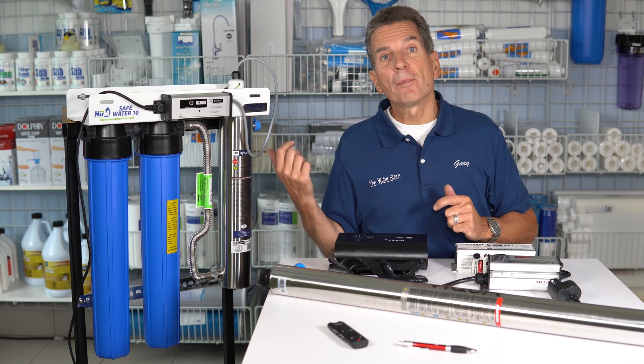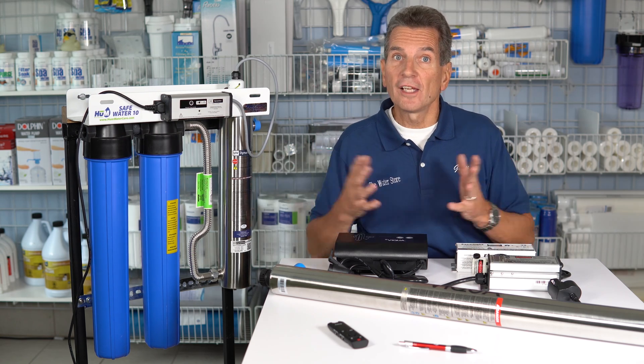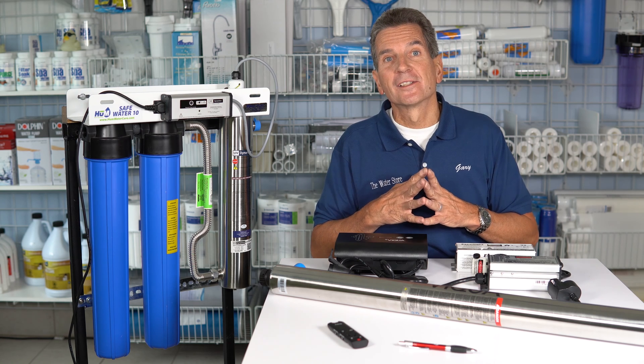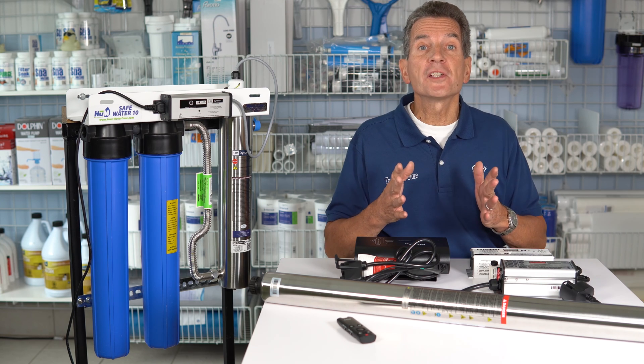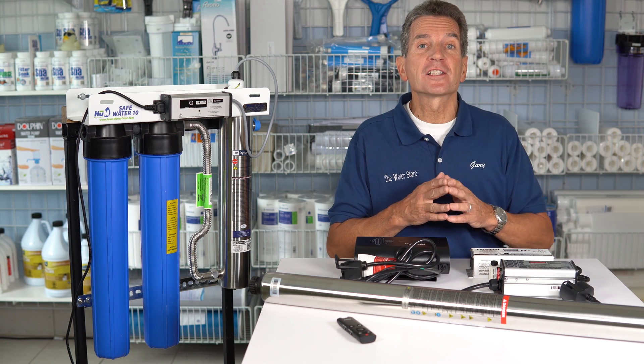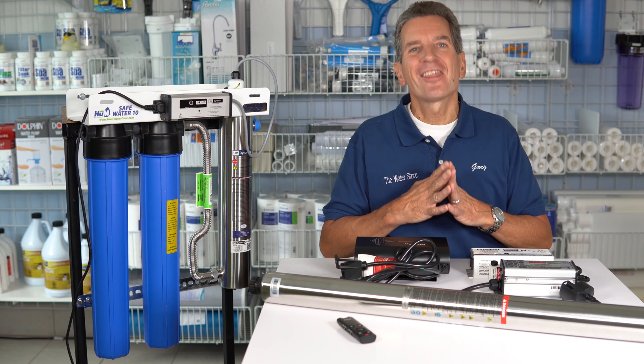If you swap in the old lamp and it's still beeping, then it's probably the controller — the controller may very well be defective. They do have a life expectancy of usually about five to seven years, so that may need to be replaced. If you like what you saw today, please click the subscribe button. For more information, go to WaterEStore.com or WaterStoreMidland.com, and that playlist on ultraviolet disinfection is right up here — click on it for lots of great information. I'm Gary the Water Guy, thanks for watching.